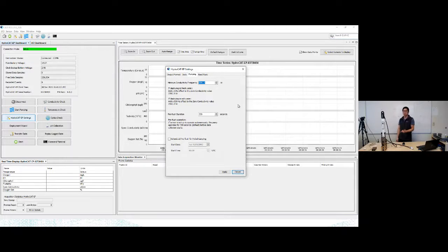We don't want this pump to run in air. Doing so will damage the impeller on the pump. So we have this setting called the minimum conductivity frequency to tell the instrument, hey, if you're not meeting this minimum frequency right here, that tells me that you are not in water, therefore do not turn on the pump.